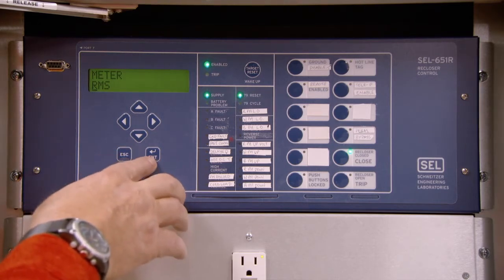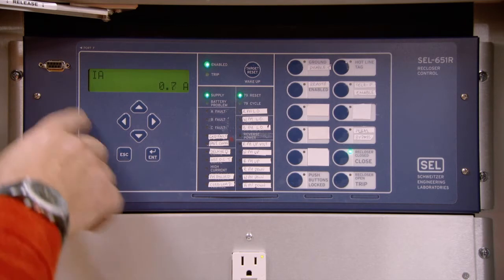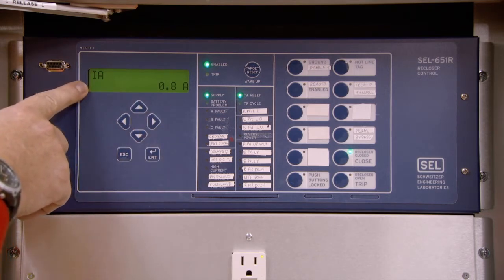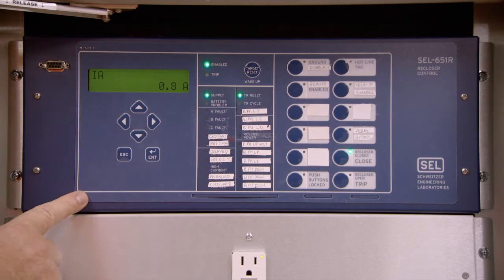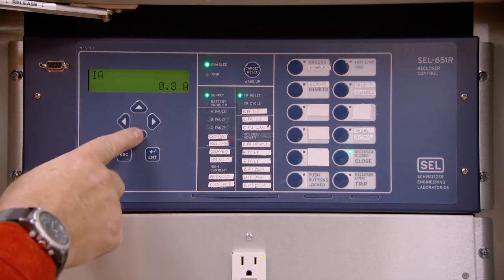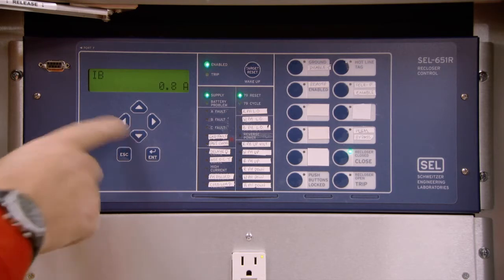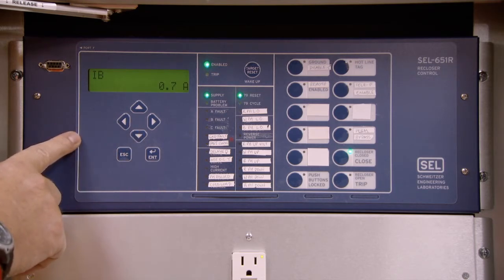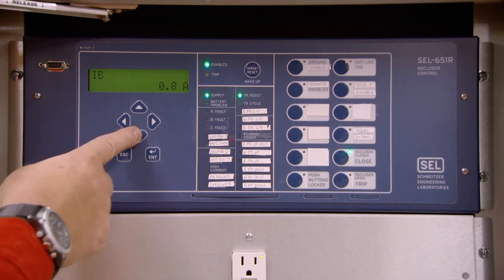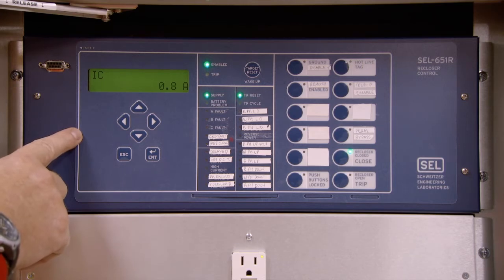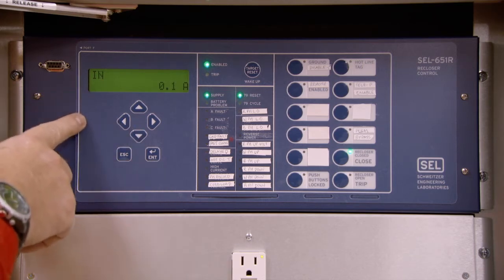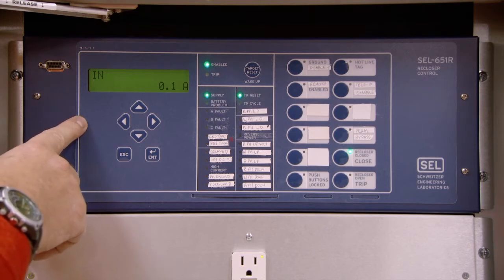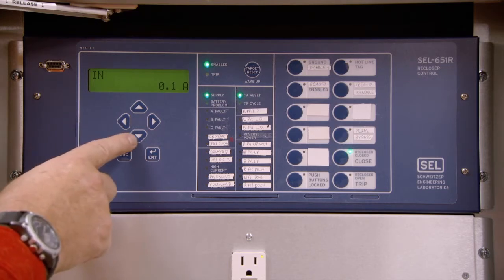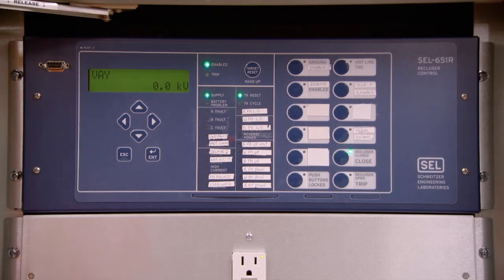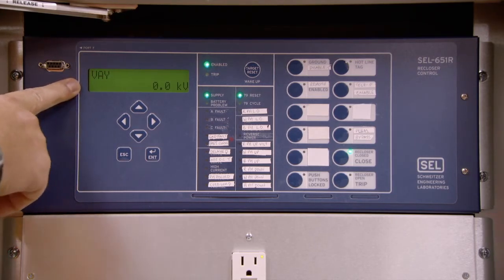If one were to go deeper into the meter menus and select RMS metering by pressing the Enter button, the A phase would be identified on the screen in the upper left-hand corner, while the amperage that is actually being applied to the unit would appear in the bottom right-hand corner. The B phase would appear and the screen will indicate the individual amperage going through in RMS current. Takes us to the C phase with the RMS current displayed. Takes us to the IN or neutral, where the screen will indicate the actual supplied neutral value rather than a calculated value. The VAY voltage would be the A phase from the load side voltage supply on the actual recloser itself.